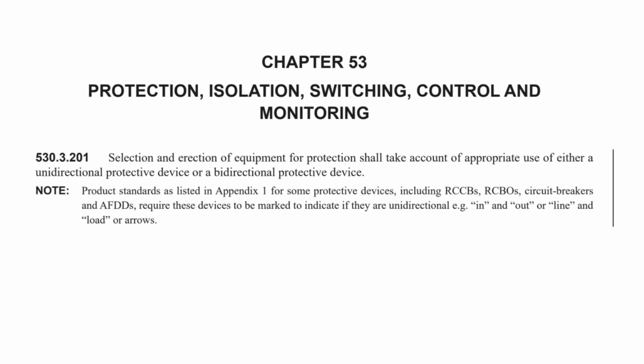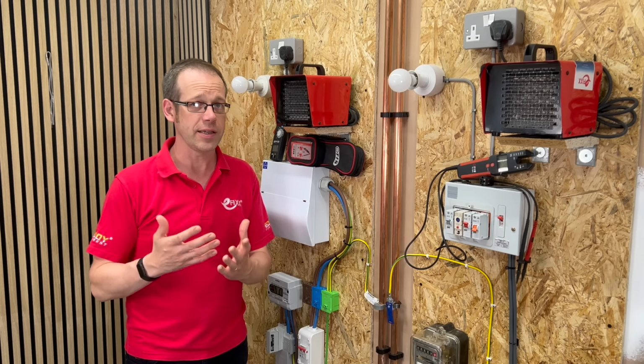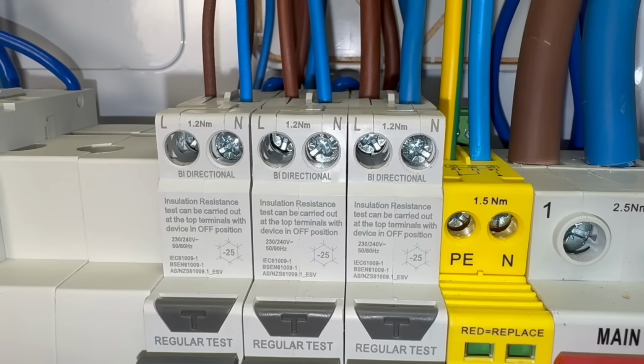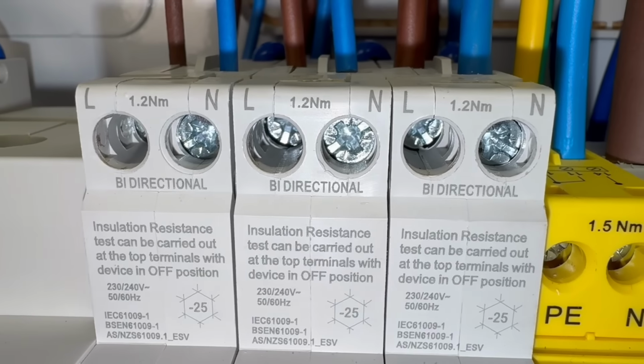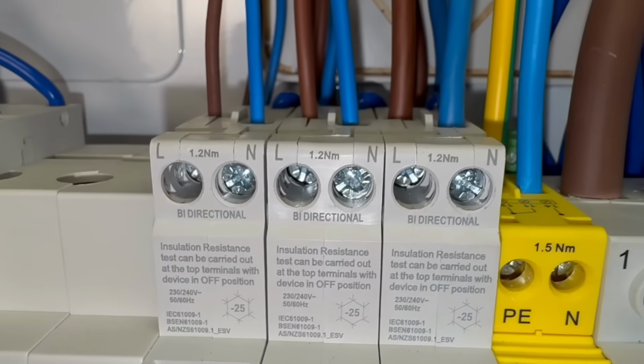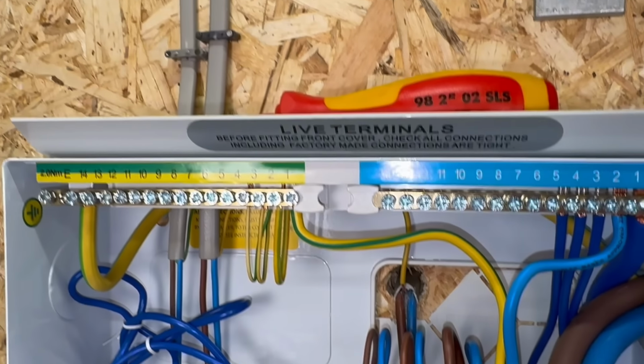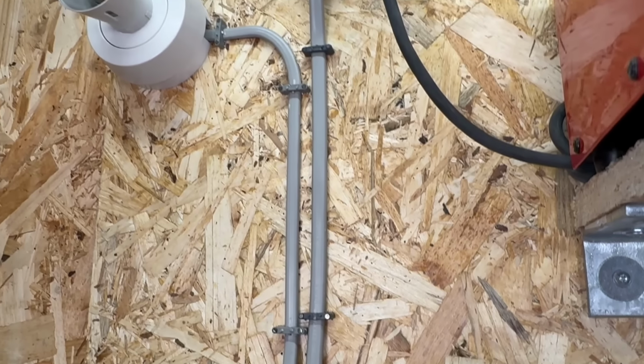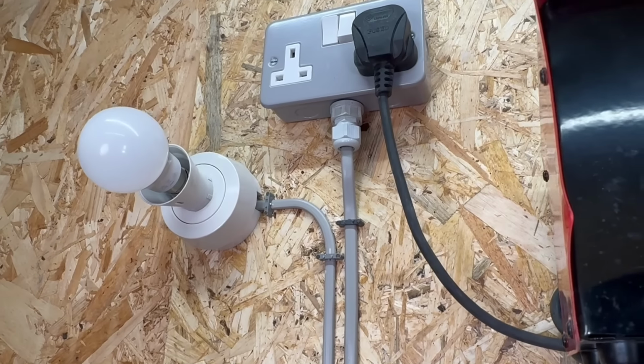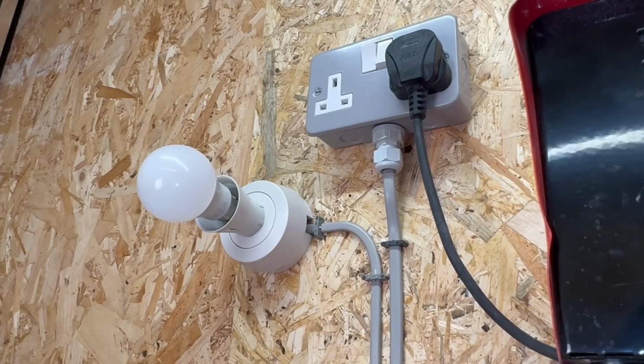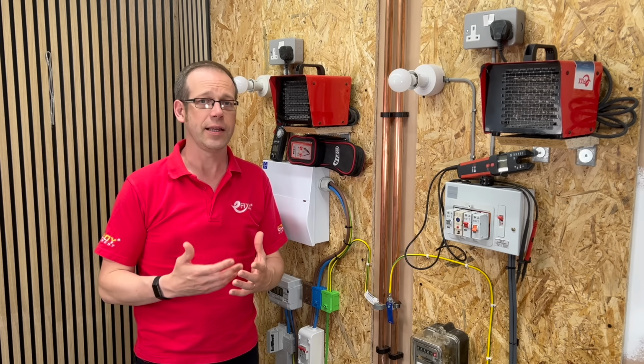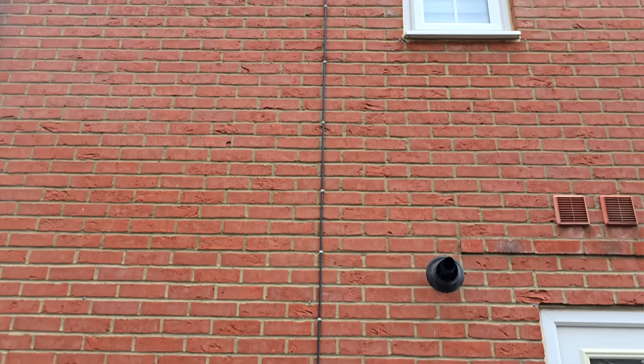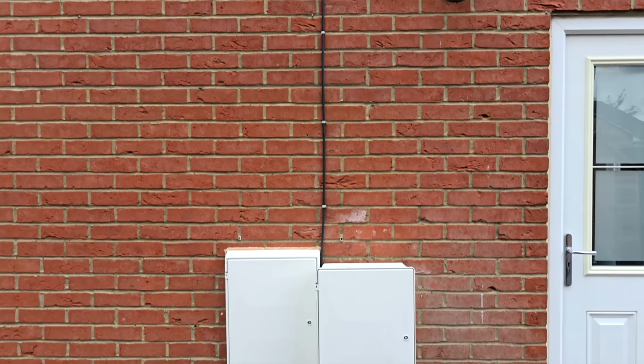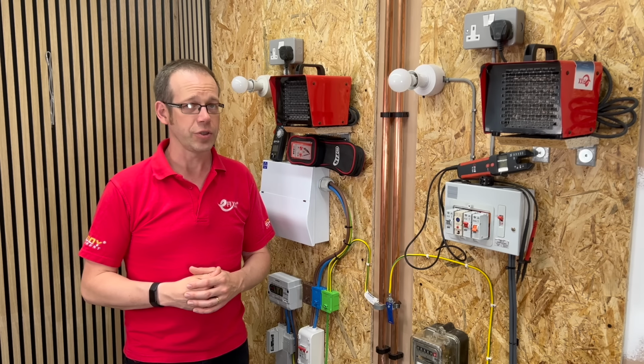Regulation 530.3.201 states that the choice of protective device must consider whether a unidirectional or bidirectional device is appropriate. It doesn't ban unidirectional devices, they're still suitable for circuits without power generating equipment. However, this led to electricians panicking a bit and starting to specify and install bidirectional devices on every circuit. This isn't necessary and can be a bit of an issue as there is a slight cost difference between the two. The bottom line is, if there's no power generation on the circuit, a unidirectional RCBO is fine and probably cheaper. If there is, use a bidirectional one. Note that we're referring to circuit there, not installation. This building has PV installed, but it isn't connected through the internal consumer unit and therefore no bidirectional devices are required here. Terminal markings and datasheets will help you choose correctly.